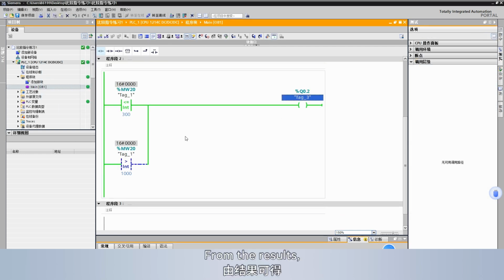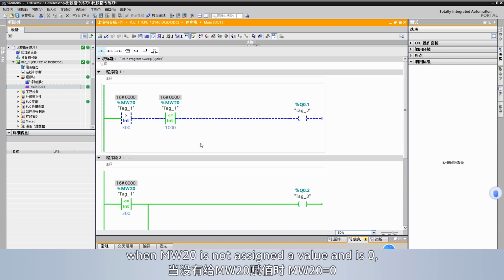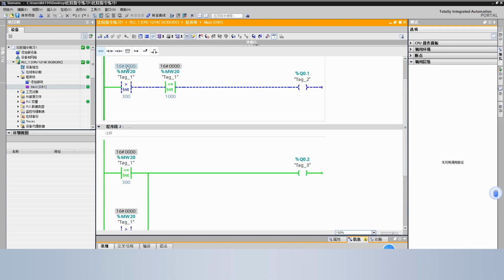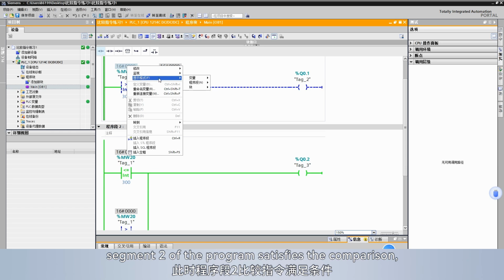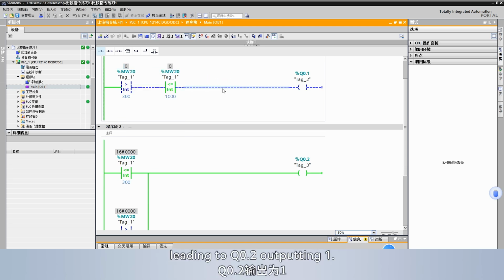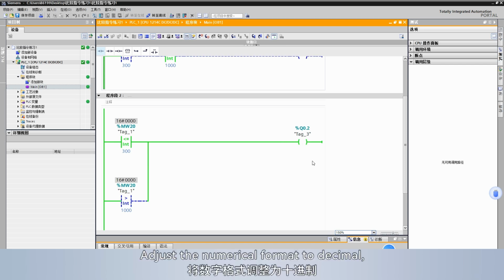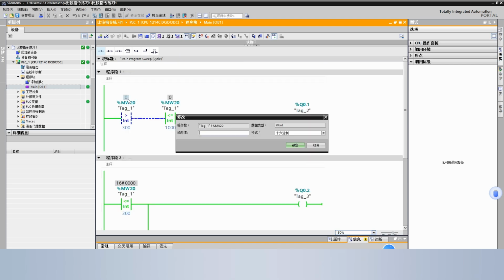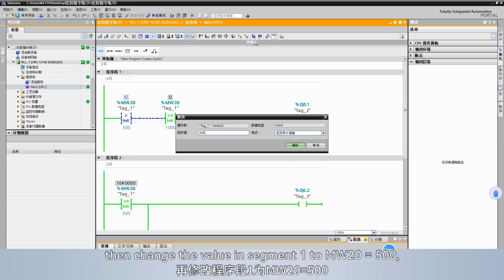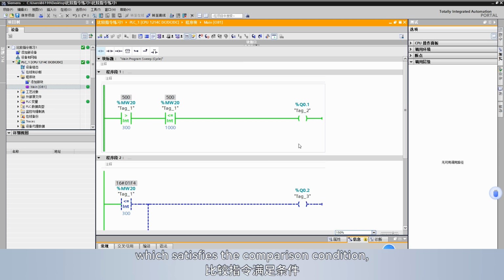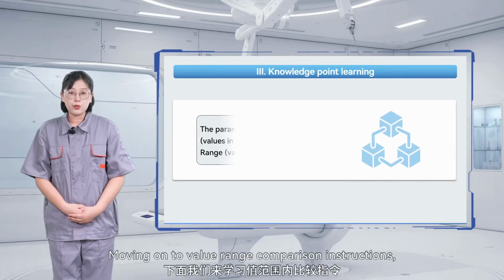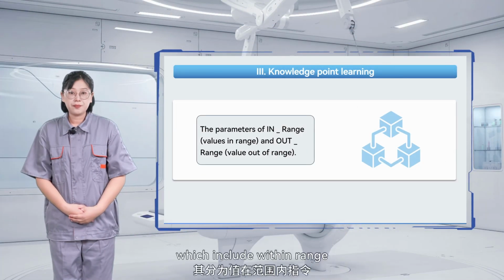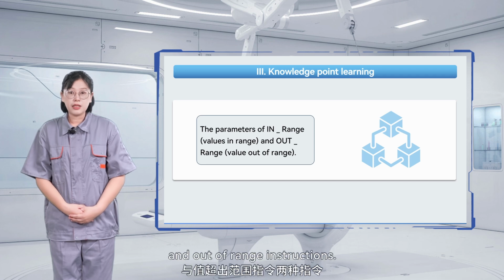From the results, when MW20 is not assigned a value and is 0, segment 2 of the program satisfies the comparison, leading to Q0.2 outputting 1. Adjust the numerical format to decimal. Then change the value in segment 1 to MW20 equals 500, which satisfies the comparison condition, resulting in Q0.1 outputting 1.